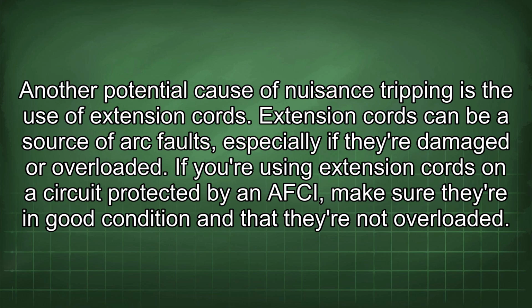Another potential cause of nuisance tripping is the use of extension cords. Extension cords can be a source of arc faults, especially if they're damaged or overloaded. If you're using extension cords on a circuit protected by an AFCI, make sure they're in good condition and that they're not overloaded.